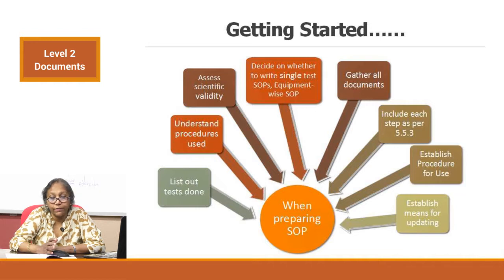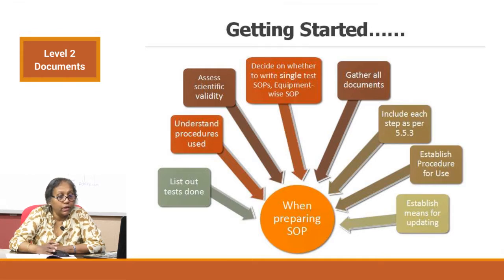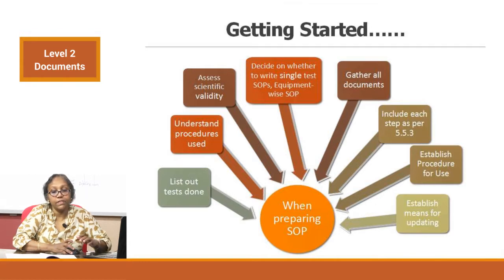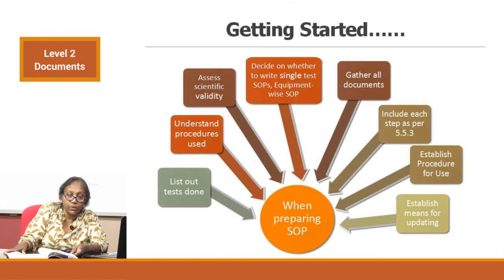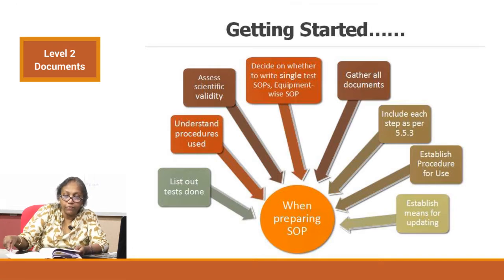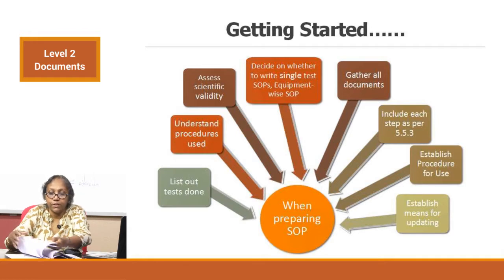Make sure you put all your documents together before getting started. The documents required for writing your SOP will include kit inserts, manufacturer's instructions, textbooks, other SOPs for the same methods, lab policies on quality control, lab policies on reporting, clinicians' inputs on critical alerts, and any other relevant documents. Make sure you have all of them when sitting down to write your SOP. Include each step as per clause 5.5.3 of the standard — that is your examination procedures, specifically 5.5.3: documentation of examination procedures.